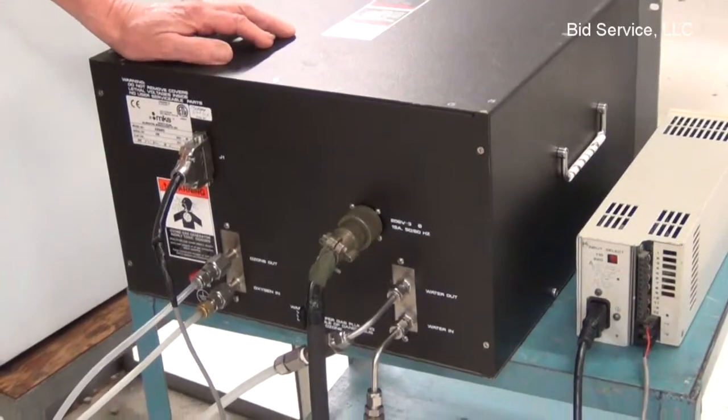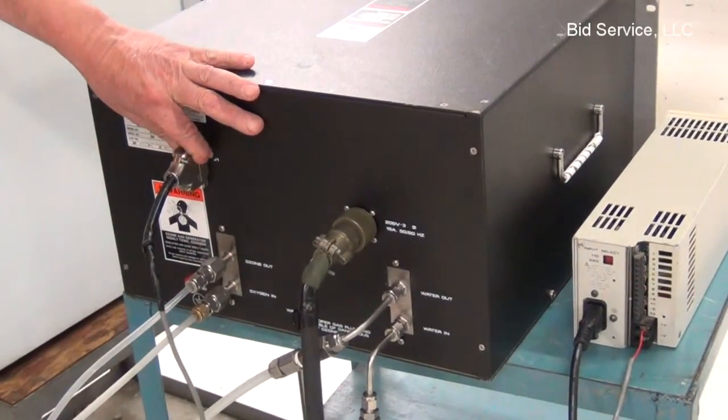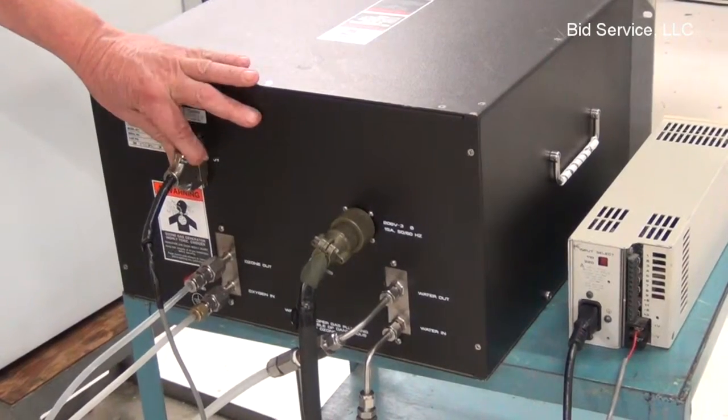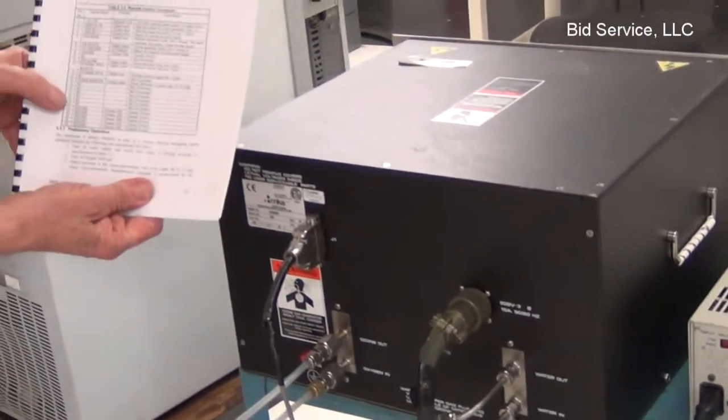The connections consist of, first, a 24-volt interlock. The pinouts for this interlock are in the service manual, so it's easy to configure.